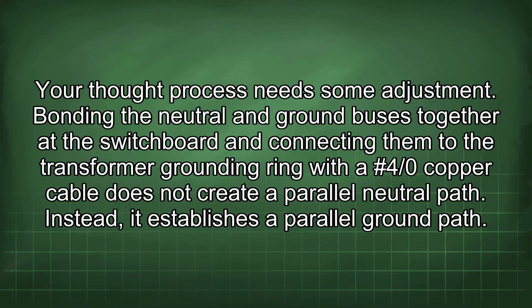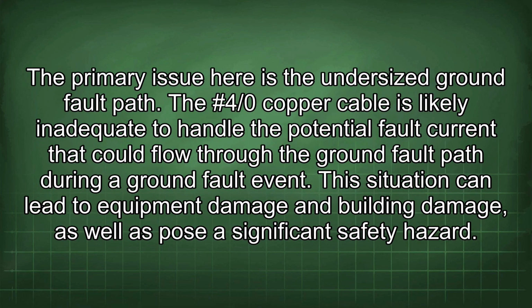Your thought process needs some adjustment. Bonding the neutral and ground buses together at the switchboard and connecting them to the transformer grounding ring with a #4/0 copper cable does not create a parallel neutral path. Instead, it establishes a parallel ground path.